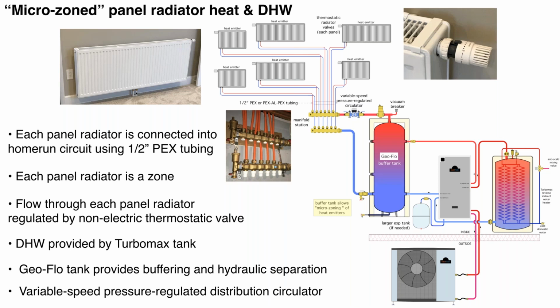And you'll see the two 1/2-inch tubes coming up here through the floor. In this case, it's 1/2-inch PEX aluminum PEX, but that could easily be PEX tubing. It could be copper. There's adapters for all different types of piping connected to the radiator. There actually is an isolation valve set up at the bottom here. But the nice thing about a panel radiator is that you get both radiant heat output from the face of the panel, as well as some convective output. So you definitely get what I would say is a higher level of comfort based on that radiant output.